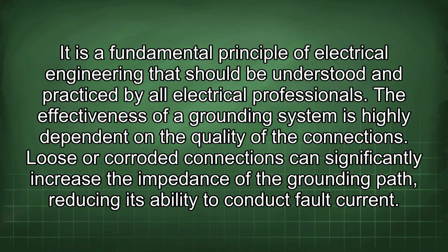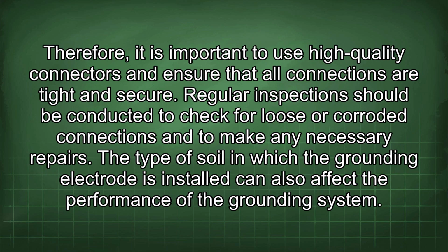The effectiveness of a grounding system is highly dependent on the quality of the connections. Loose or corroded connections can significantly increase the impedance of the grounding path, reducing its ability to conduct fault current. Therefore, it is important to use high-quality connectors and ensure that all connections are tight and secure. Regular inspections should be conducted to check for loose or corroded connections and to make any necessary repairs.